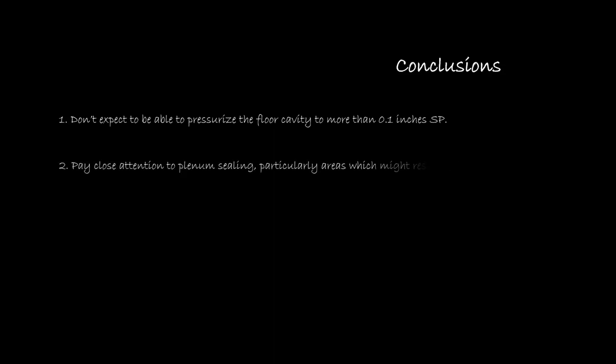In conclusion, let's summarize a few points to consider when designing UFAD systems. First, design for plenum pressures between 0.05 and 0.1 inches, which will minimize plenum leakage and diffuser noise. Secondly, pay close attention to plenum sealing, especially at its vertical boundaries, to avoid type 2 leakage. Be aware of thermal decay and have a plan to minimize its effect.